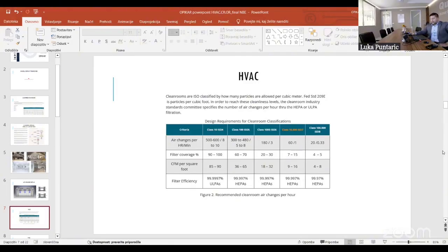We can go on to filter coverage. The whole clean room ceiling needs to be equipped with HEPA or ULPA filters, high efficiency particulate filters. So in the case of ISO 8, 4 to 5%, up to 100% in ISO 4. So the whole ceiling also needs to be equipped with high efficiency HEPA absolute filters. You can see how this differs from class to class.